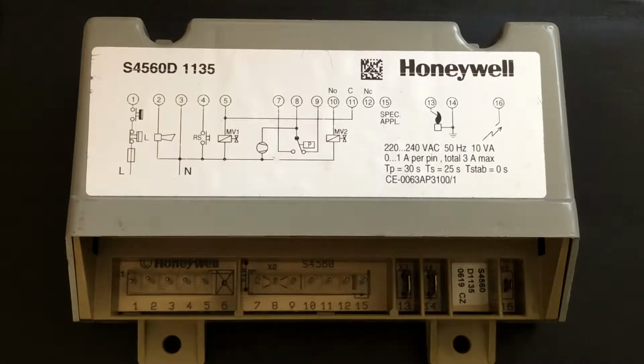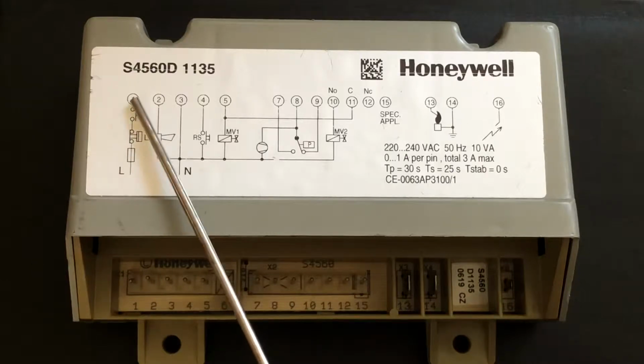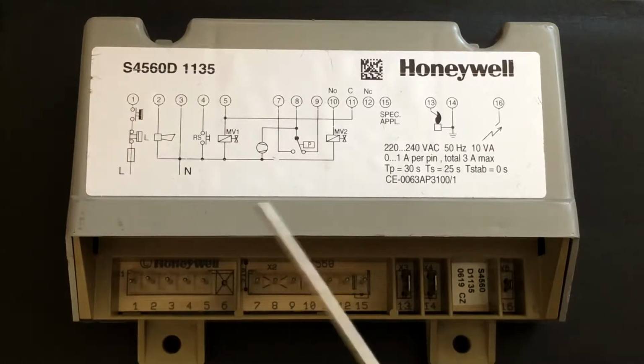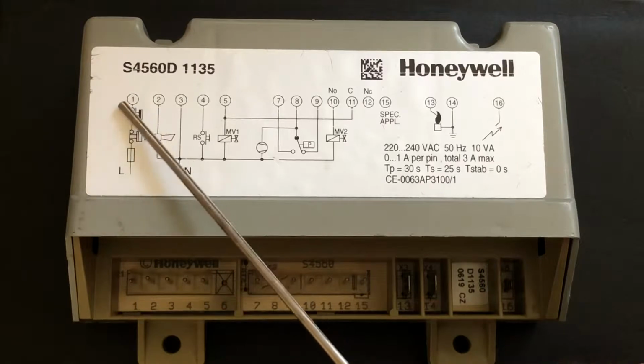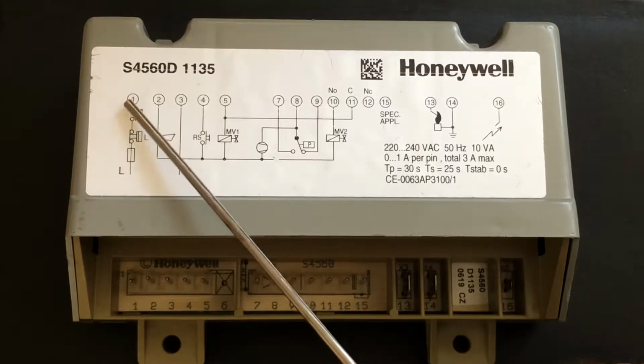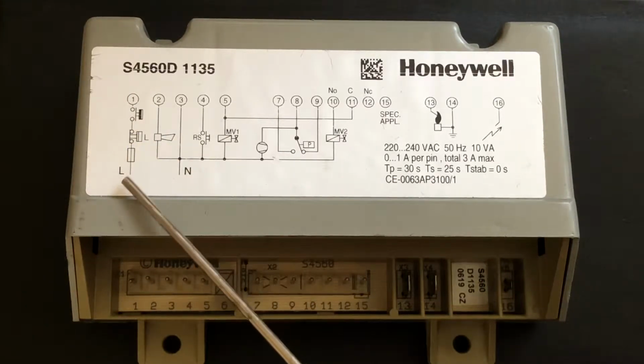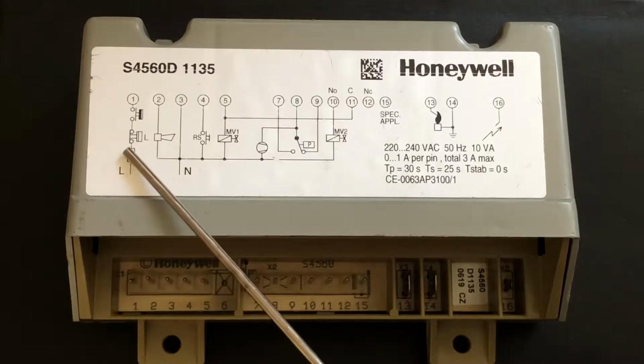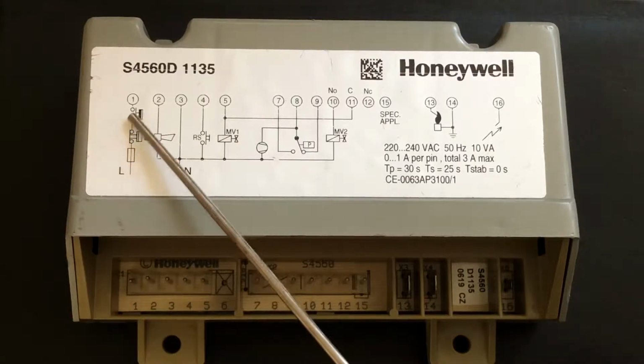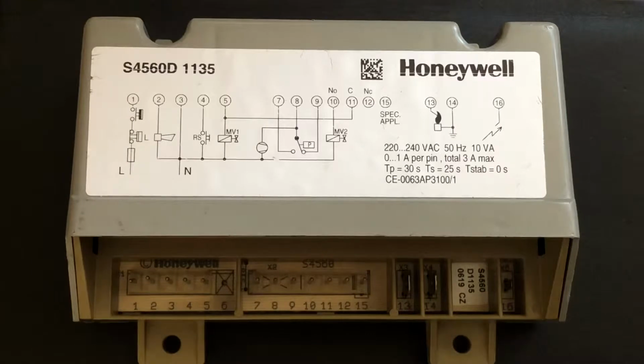whether you have power at this point, at number 1. Number 1, you're supposed to have power. You can bring the power to this Honeywell controller via a thermostat or a logic control. Anything that provides power to number 1 is okay. As you see here, you have to have the fuse, then the switch, and you can have the thermostat, and then the power supply into this module.